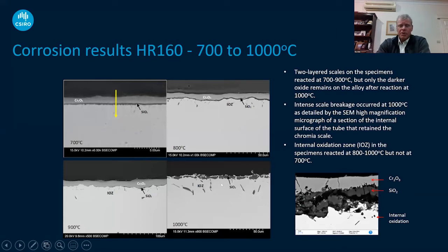Here are some corrosion results from work we've done looking at what happens with supercritical CO2 over various types of steel. In this case, HR160 is the base metal. At 700 degrees Celsius, the supercritical CO2 flowing over the steel forms a protective layer. At 800 degrees C, that chromium layer is still there, along with a small silica layer. At 900 degrees C, it's still there. But note that somewhere between 900 and 1,000 degrees C, that scale has broken off, which can cause real problems in the turbine or in the printed circuit heat exchanger recuperators. So you have to be very careful about material corrosion issues in these high temperature steels.